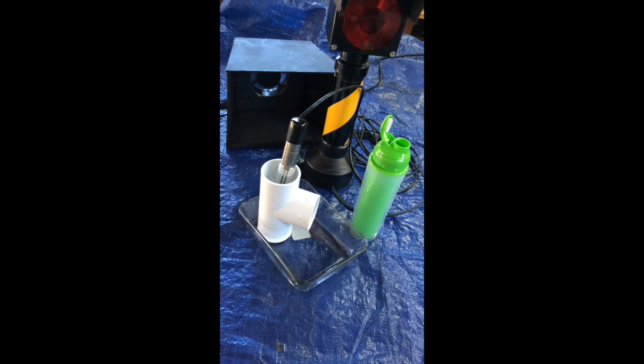Okay, we're back for phase 3 of the test. It's now 11:27. It took about 10 minutes, I guess, for the naphtha to evaporate and the system to reset. Again, the latch was set, the flasher was flashing, and then periodically you push the test and reset button to see if the sensor had reset. When the sensor is not in alarm, the reset button down here also acts as a test button.